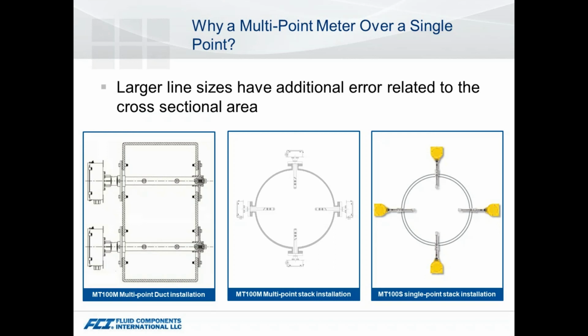So line size is one area to take this approach. The other area might be due to lack of straight run, because the other thing you deal with in these large size lines is straight run issues on a common basis. That's a lot of real estate to have to cover. So we have different approaches with the metering as far as the number of points we can put into the system.